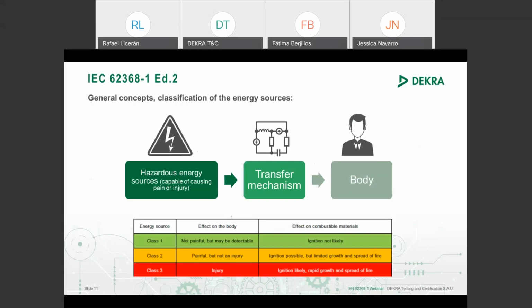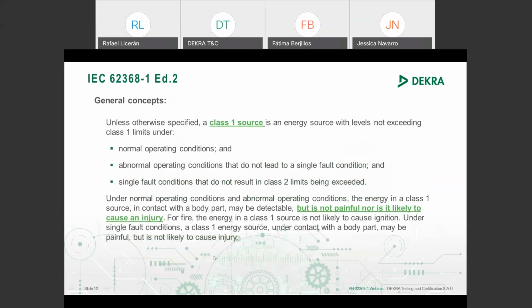And we have a last class. This is Class 3, energy source Class 3. The red color is used to identify it, and this class of energy can cause injury, and the user cannot access this kind of energy. In this way, a Class 1 energy source is always safe in normal operation, in abnormal operation, and in single fault conditions. You are always safe touching a part that has Class 1 energy.